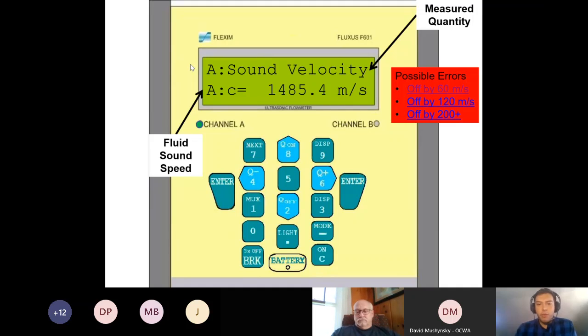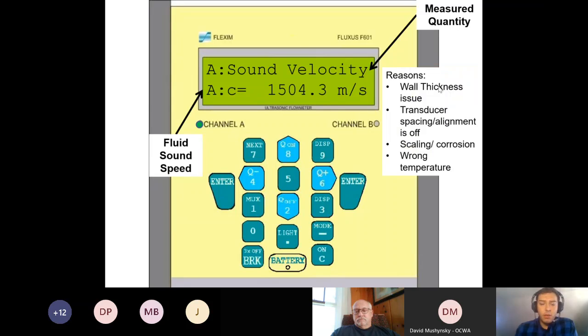So if I was at 1435, that would be at the low end of acceptable, and same thing with the high end. But if you're more than 50 meters per second off from what you should be, this is usually a wall thickness issue. So maybe you chose the wrong schedule of the pipe. You thought it was schedule 40 and it's really schedule 80. It could also be strong buildup in the pipe.